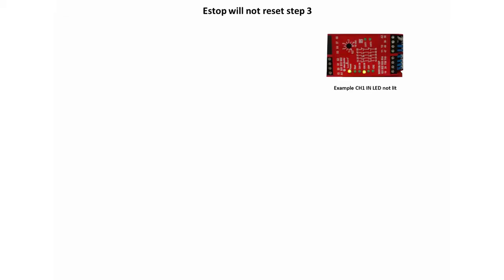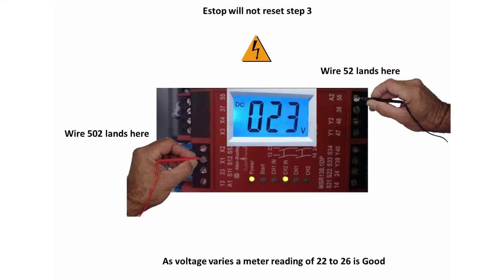If the CH1 IN is not lit, place the positive lead on wire number 502, screw terminal S12 on SR1. If you have 24 volts, then SR1 needs to be replaced.